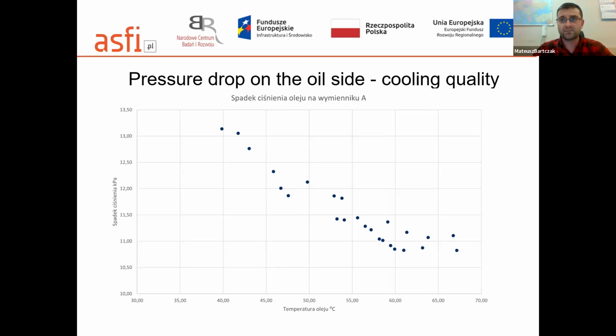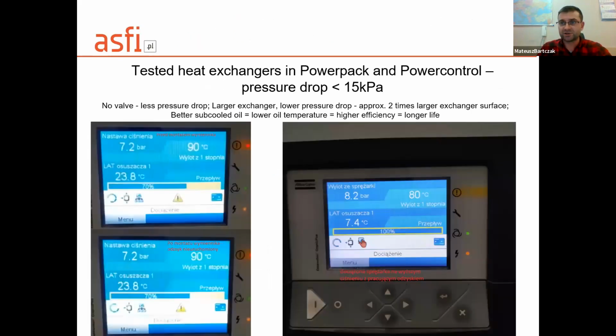Where it's important is when the compressor's work changes, when the compressor goes on load to full load, with a very big speed change, and the compressor accelerates rotation from 20% to 100%. During acceleration, the pressure drop increases to the second power. So if you have a big heat exchanger, you have a low pressure drop, and then you can keep the same cooling conditions as in a compressor without a heat exchanger.